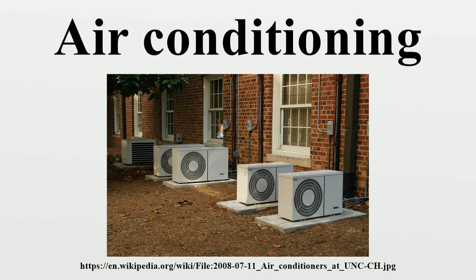Evaporative cooling in very dry climates. Evaporative coolers, sometimes referred to as swamp coolers or desert coolers, are popular for improving coolness during hot weather. An evaporative cooler is a device that draws outside air through a wet pad, such as a large sponge soaked with water. The sensible heat of the incoming air, as measured by a dry bulb thermometer, is reduced. The total heat of the entering air is unchanged. Some of the sensible heat of the entering air is converted to latent heat by the evaporation of water in the wet cooler pads. If the entering air is dry enough, the results can be quite substantial.